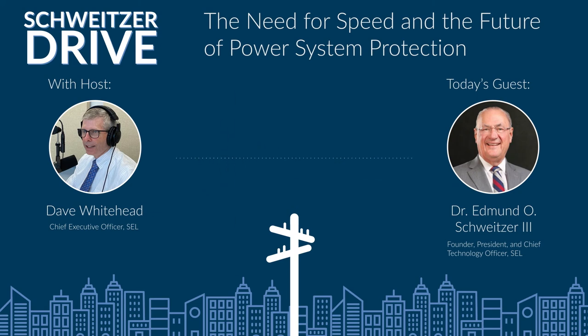One, the speed of light, and that dominates. And the other one is, frankly, our processing interval. So we got the processing interval down to about 100 microseconds, and nothing we can do about the speed of light. So go back to that 100-mile line and get a fault right in the middle, Dave and I see it 300 microseconds later. And if I tell Dave and Dave tells me, then that's going to be, well, a whole line, that would be 600 microseconds if we do it in glass.